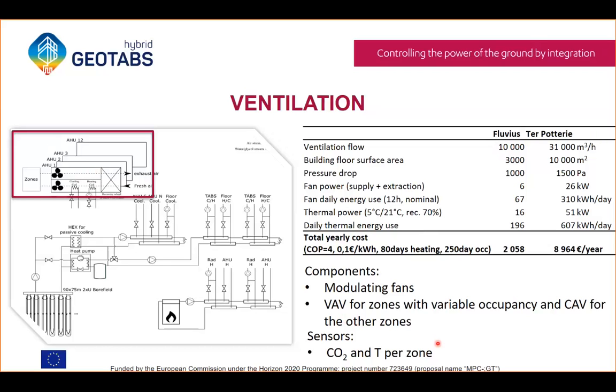In the case of the MPC at Fluvius, we were able to save up to 60% sometimes on the ventilation. These are significant numbers. Obviously, for this, we also need sensors to be able to measure the CO2 concentration and the temperature per zone to ensure that comfort is still guaranteed.